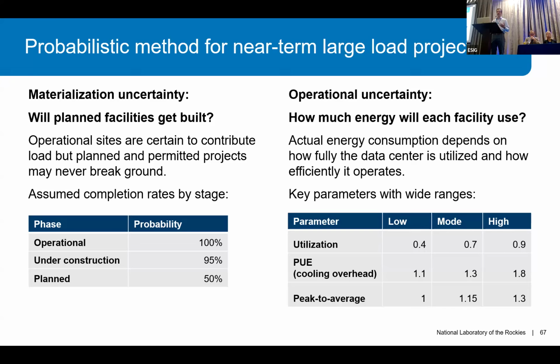For facilities selected from our sample, there's a lot of uncertainty in their operations. Three key areas where we create probability distributions are utilization—think of this as a capacity factor for the load—and the cooling overhead, or power usage effectiveness, a term from the data center industry describing how efficient cooling systems are relative to IT loads. This can vary dramatically by cooling technology and really impact overall annual load, especially during heat waves and periods of high cooling needs. This parameter can be critical for understanding the load the grid needs to serve.